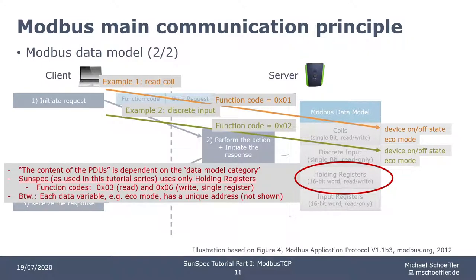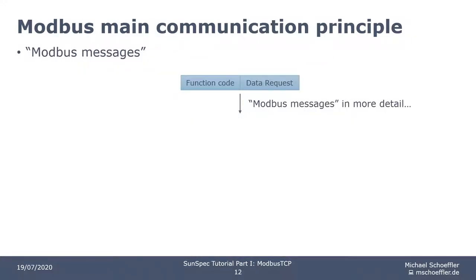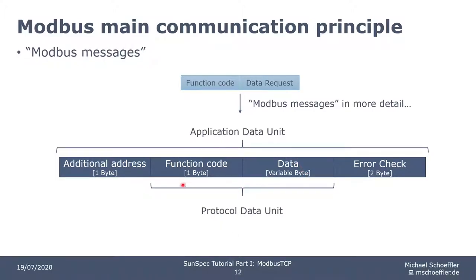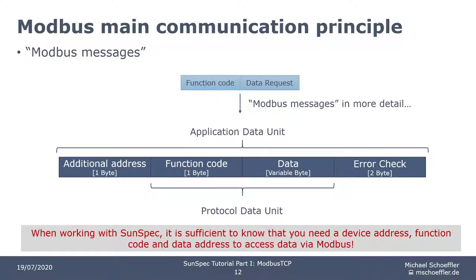It might also be important to know that each data variable accessible via Modbus has a unique address. Let's have a deeper look into messages sent via Modbus. You already know the inner part of PDUs — the function code and the data field. Typically, each protocol implementation of Modbus, for example Modbus over Serial Line or Modbus TCP, requires adding some more data to the PDU. In the specification documents, this data overhead is represented as additional address and error check. The PDU with the protocol-specific data overhead is called an Application Data Unit (ADU). For SunSpec, it's basically sufficient to know that you need a device address, function code, and data address in order to communicate with devices.